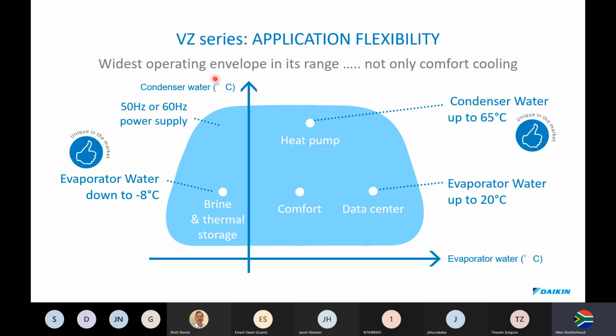applications and advantages in operating envelopes within this chiller down to -8. You can still make ice at -8 if you're doing ice harvesting. Not that it really matters for our country, but 50 or 60 hertz can plug in because we're using inverter. It doesn't matter. It's not going to affect the rotational speed of the compressor. Our power electronics determines the rotational speed of the compressor. Can generate hot water for you up to 65 degrees, and we can supply up to 20-degree cold water for data centers.